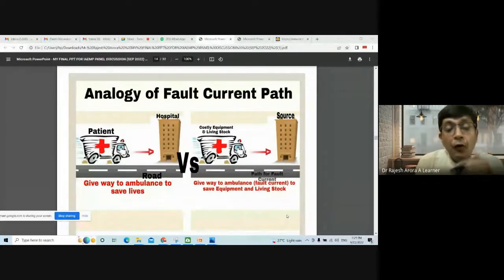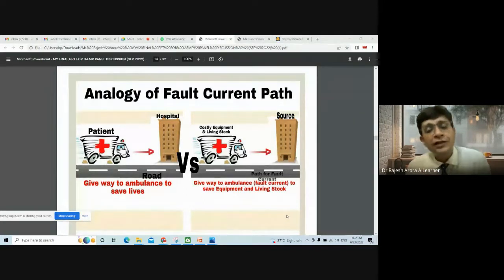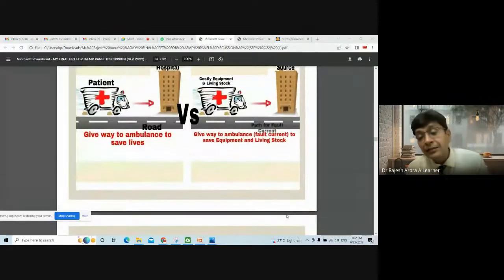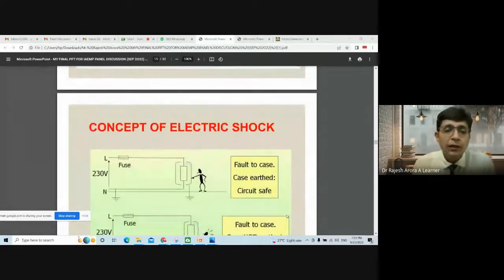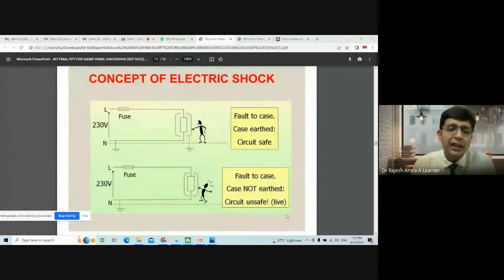And when we talk about fault and shock, your RCCB comes into the picture. The residual current circuit breaker will help you protect your life. This is an analogy of an ambulance. When you give space to an ambulance to reach the hospital in minimum time, at the same time the fault current has to go back to the source in minimum time. Otherwise, there will be disaster. People will get shocks, and there will be ignition of fire. If there is some delay in the disconnection of the system, automatic disconnection of supply is mandatory in such a scenario. This is depicted by another picture, the concept of electrical shock.